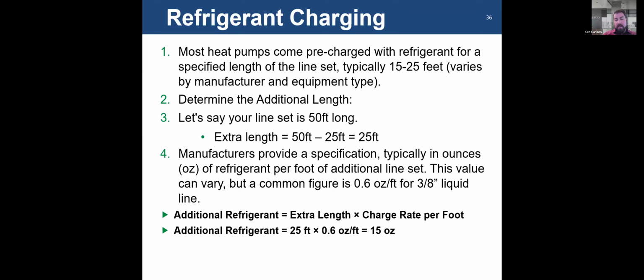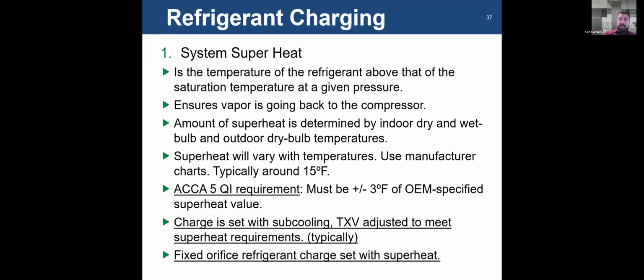Just so it's clear, it's 16 ounces to a pound. So for an extra 25 feet of line set, all you have to do is add about 1 pound of refrigerant. Keep that in mind. If you run a calculation and all of a sudden it tells you to weigh in 6 pounds of refrigerant, check your calculation again. It's unlikely that you actually need to add 6 pounds. A pound to 2 pounds is probably typical. Sometimes it's only a few ounces that you have to add.